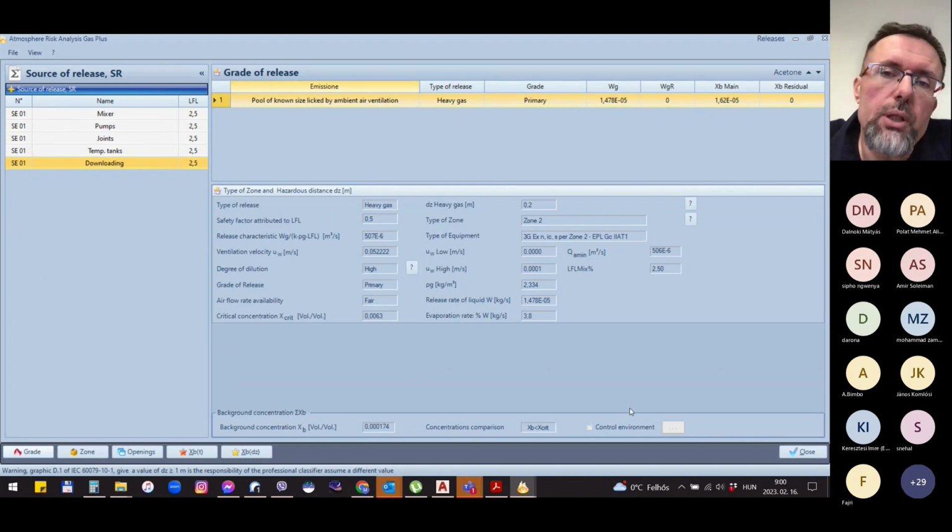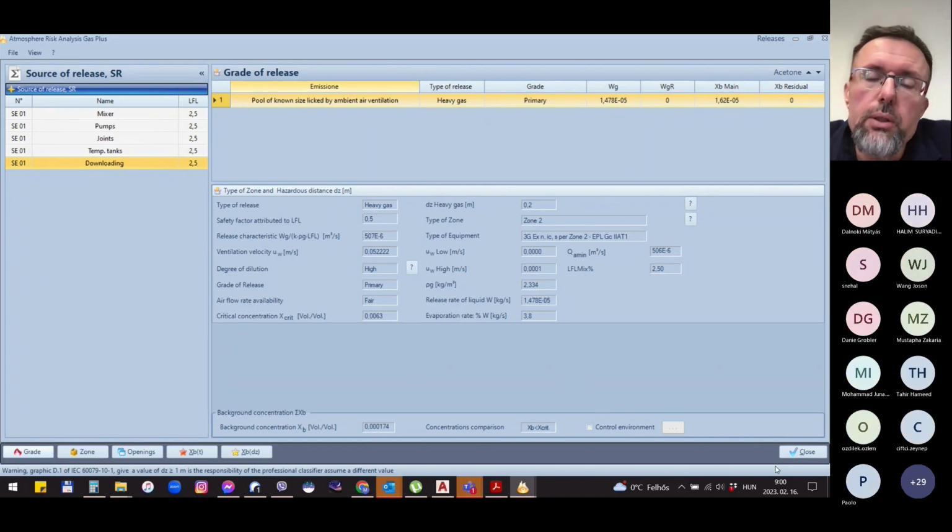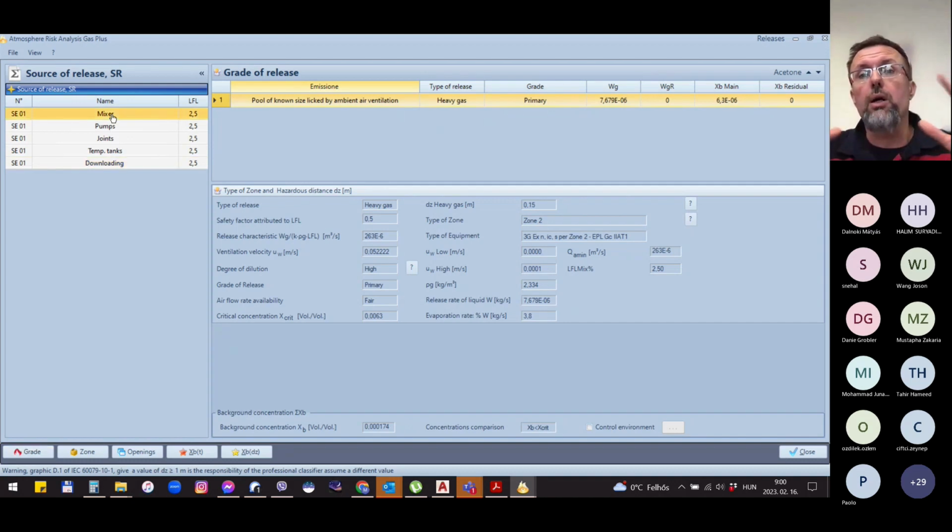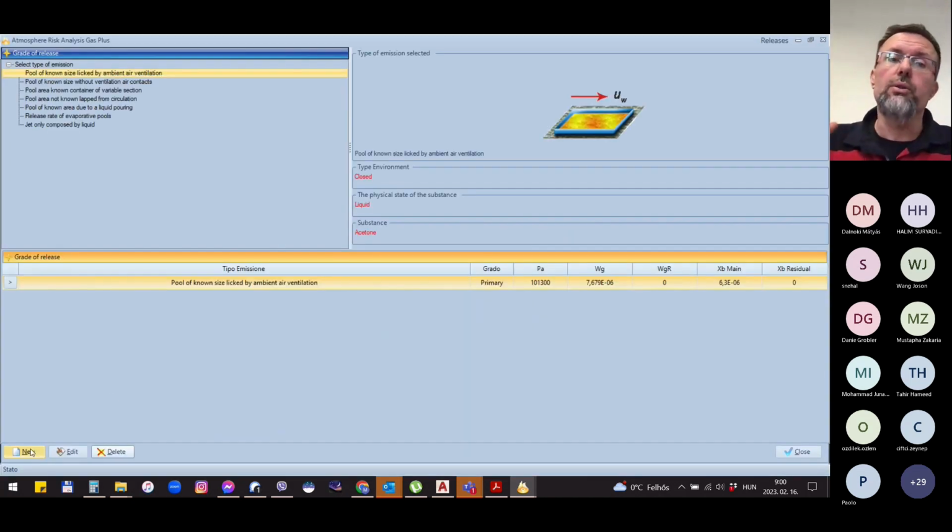But I hope that you see that if you are increasing these values, you can lower the extent. Okay, so depending when you do the hazard classification, okay, as part of design, and I would strongly recommend to do it at the basic stages, okay, because in that way, while you are doing your primary hazard classification, you can already set the parameters accordingly, according to your best interest.